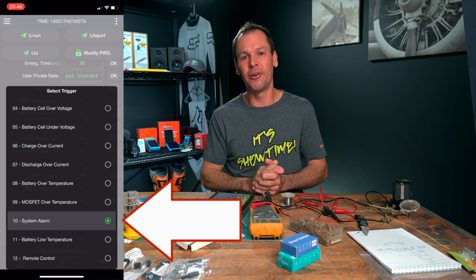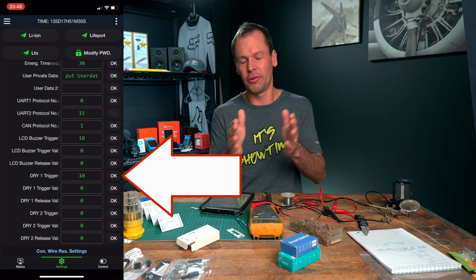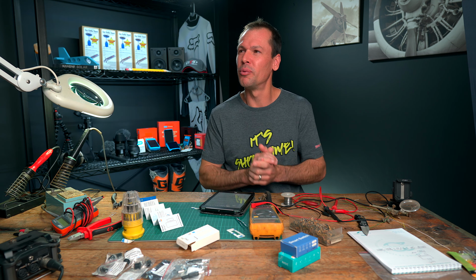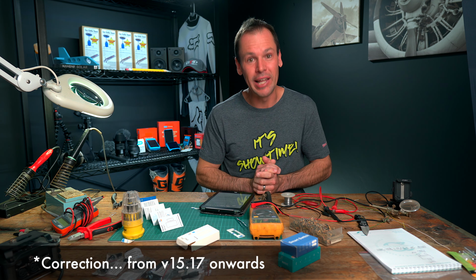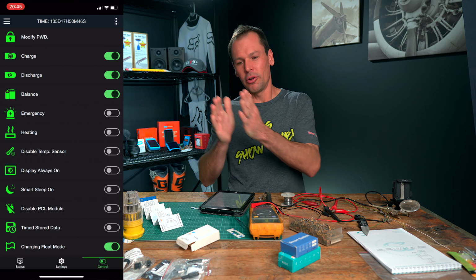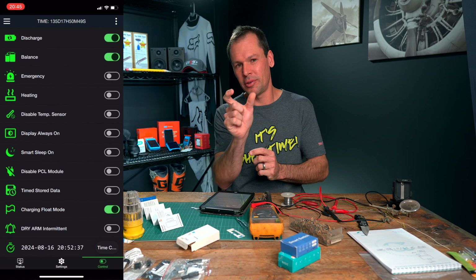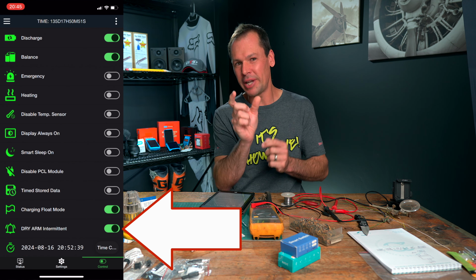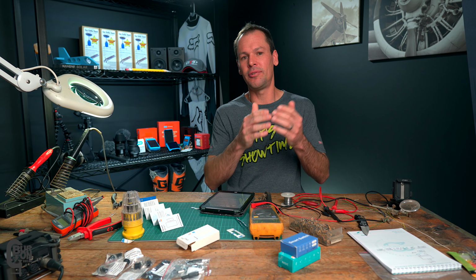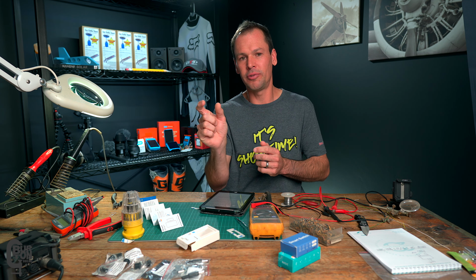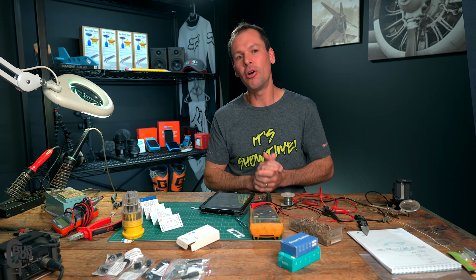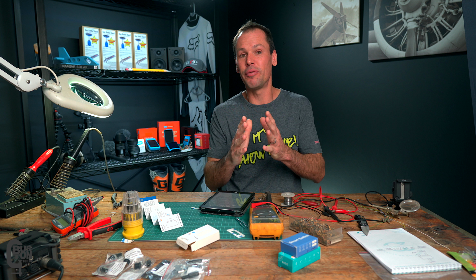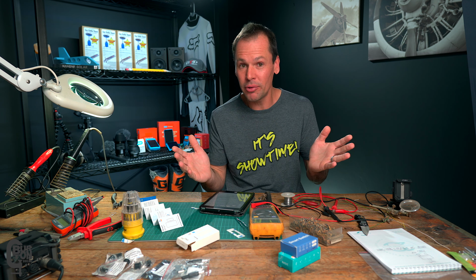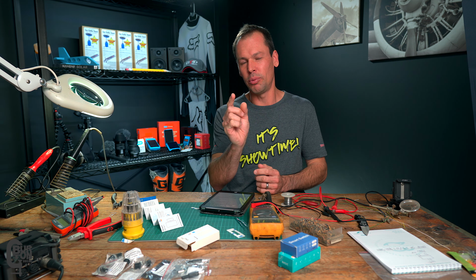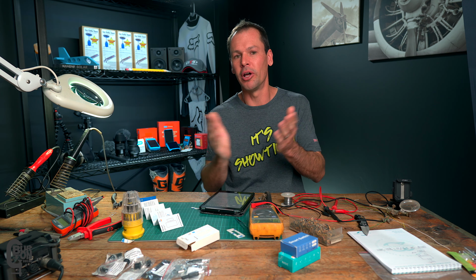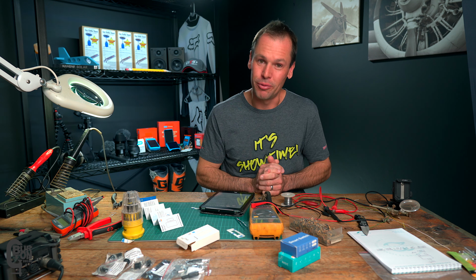If you're still a little worried about it, you could go into the BMS app, onto the control page — this is only really if you've got some of the latest firmware, I think from 15.11 onwards. Scroll down right to the bottom, and there's a setting called Dry Arm Intermittent. If you enable that setting, as soon as there's a BMS alarm, the dry contact or relay contacts close, but only stay closed for 1 minute. It doesn't matter if the alarm is still going off for 24 hours — if that setting is enabled, the contacts only stay closed for 1 minute, then open again. So that's something you guys could do if you wanted to.